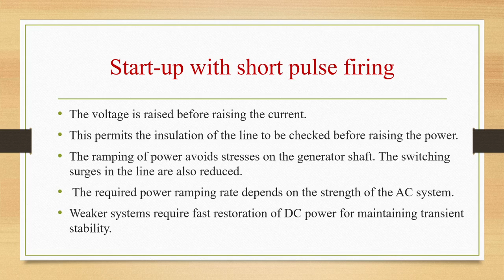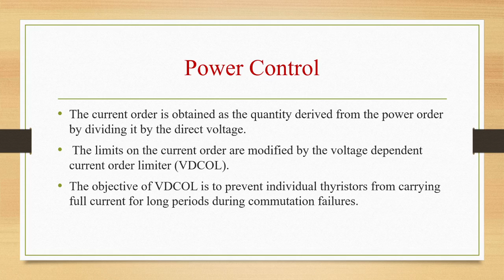Next, let us see the power control. The current order will be obtained as a quantity derived from the power order by dividing it by direct voltage. The limits on the current order are modified by the voltage dependent current order limiter, that is VDCOL. So what is the objective of this VDCOL? Objective of VDCOL is to prevent individual thyristors from carrying full current for long periods during commutation failures.